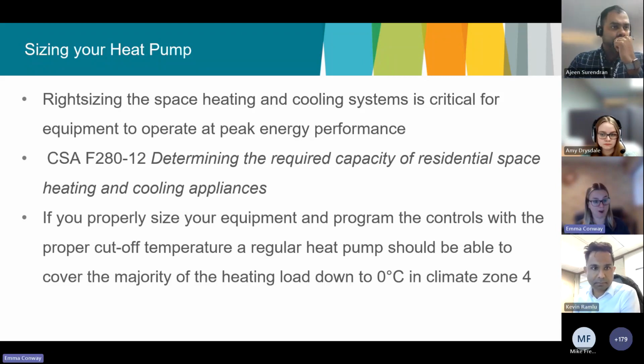If you properly size your equipment and program the controls with the proper cutoff temperature, a regular off-the-shelf heat pump should be able to cover the majority of the heating load down to about 0 degrees Celsius in this climate zone. I'm talking about climate zone 4.